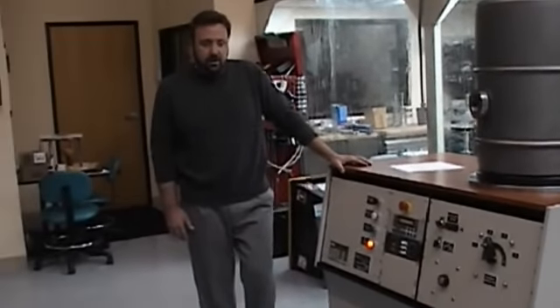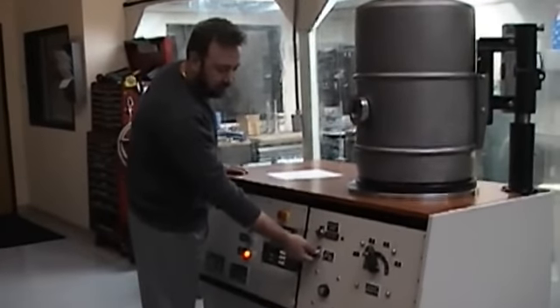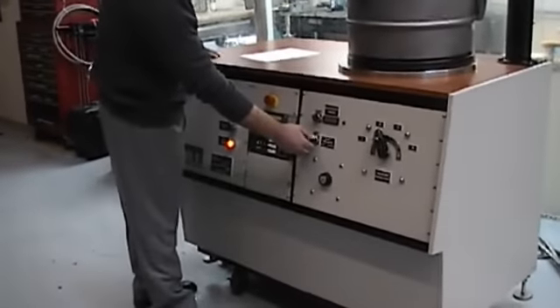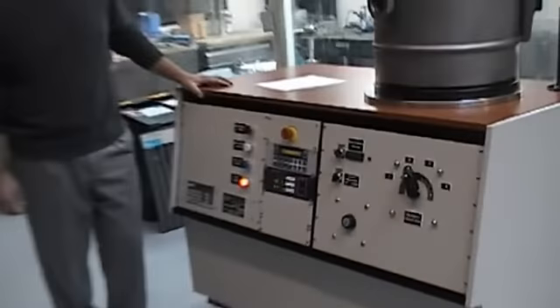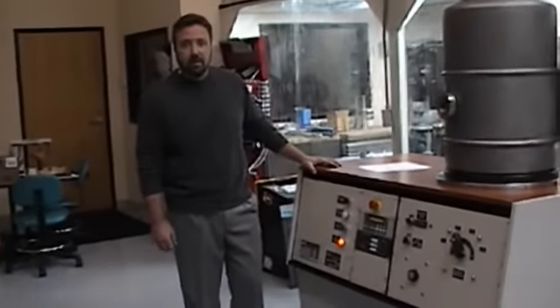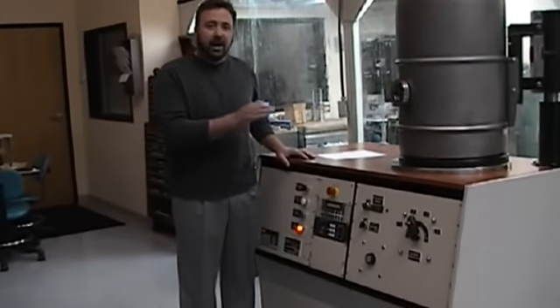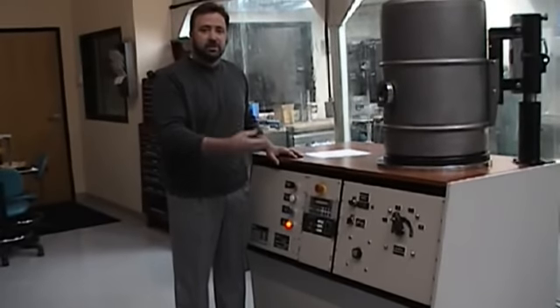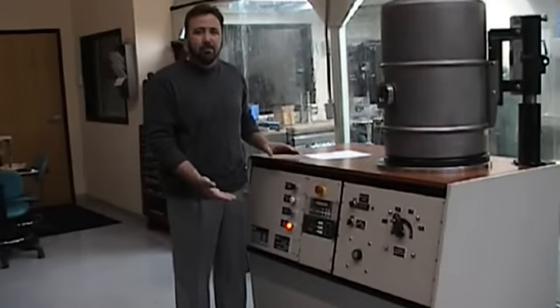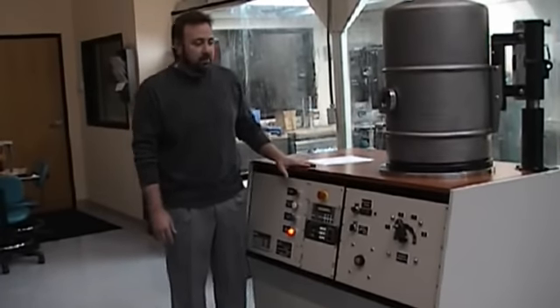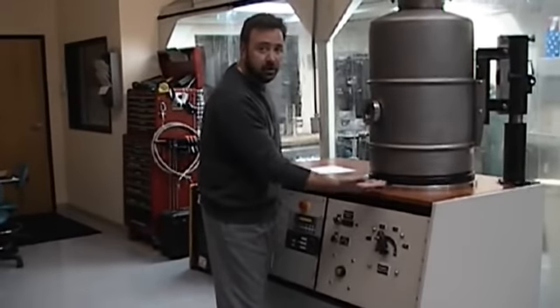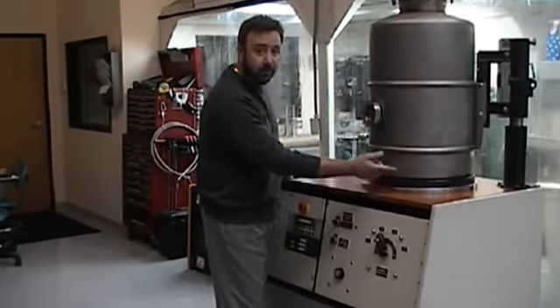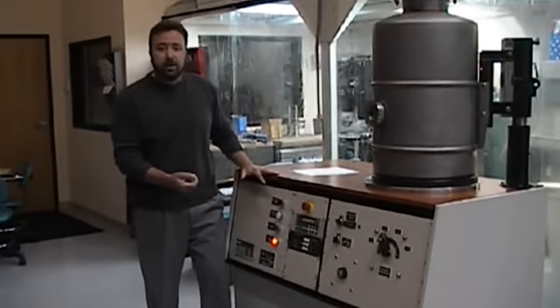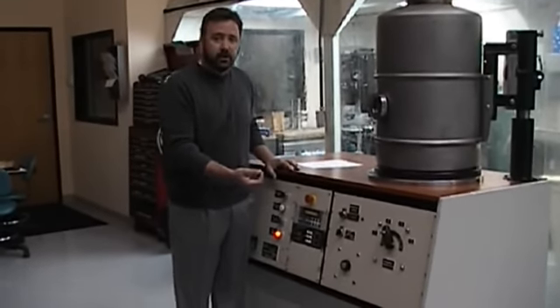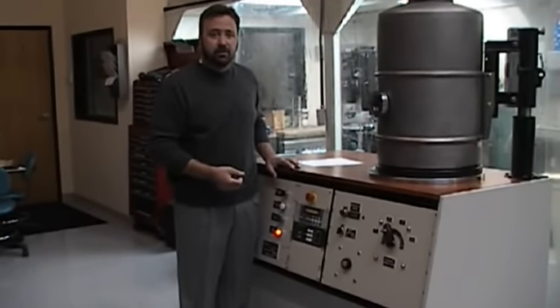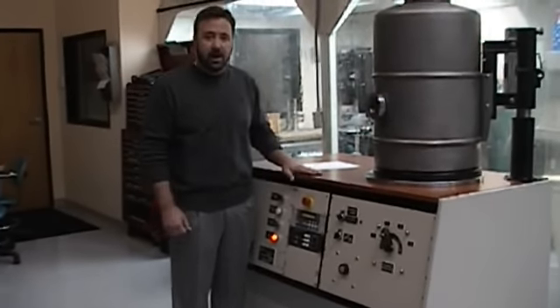We have an interlock on the bell jar that keeps the hoist from raising, or attempting to raise, while it's under vacuum. The switch is set very lightly under vacuum, meaning that it has to vent to just about atmosphere. At that point, it'll allow it to go up. The vacuum switch is located underneath the bell jar, underneath the base plate, through a feed through. It is an adjustable switch. If you ever have a situation where you need to readjust it, it is adjustable. We have set it. It should be more than adequate.